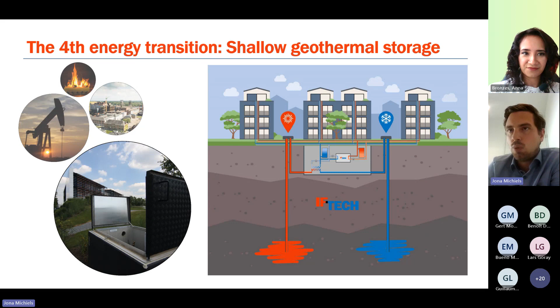So what we do is shallow geothermal energy storage. When we talk about geothermal storage, we don't go deeper than 250 meters. Most people think of geothermal going way deeper, with higher temperatures. But what we create is an underground thermal battery storage for heat and cooling, capturing summer heat and using it in winter via a heat pump with very high COP yields. In summer we do the opposite, using winter cool for cooling, with even higher COPs achieved.